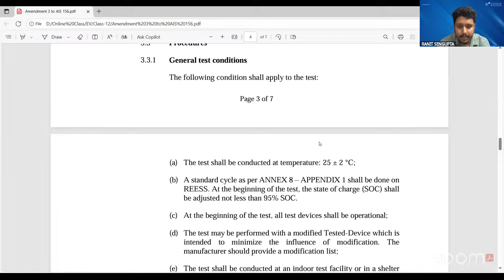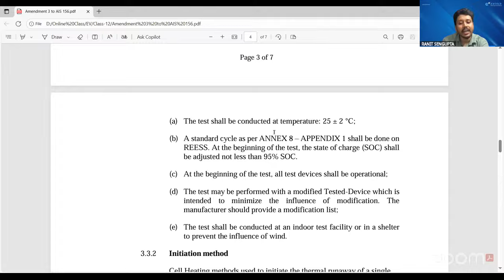We try to measure the thermal runaway, so there are given measurements for it. I'm just showing the method. You can see the clauses: the test shall be conducted at an ambient temperature of 25 plus minus 2 degrees, and the SOC, state of charge, should be 95%, which is almost full charge. At the beginning of the test, all test devices shall be operational, meaning we have to put temperature sensors also.